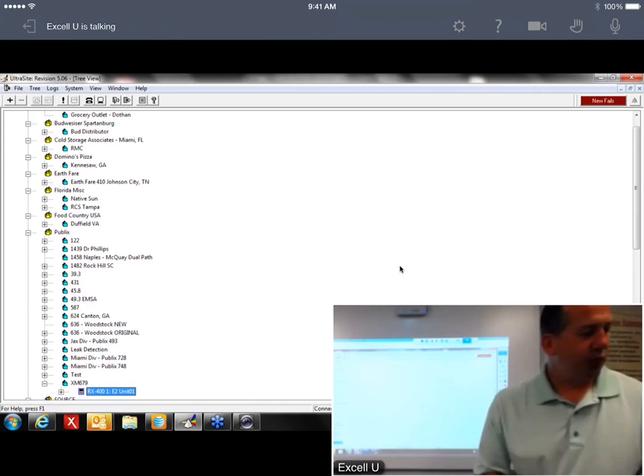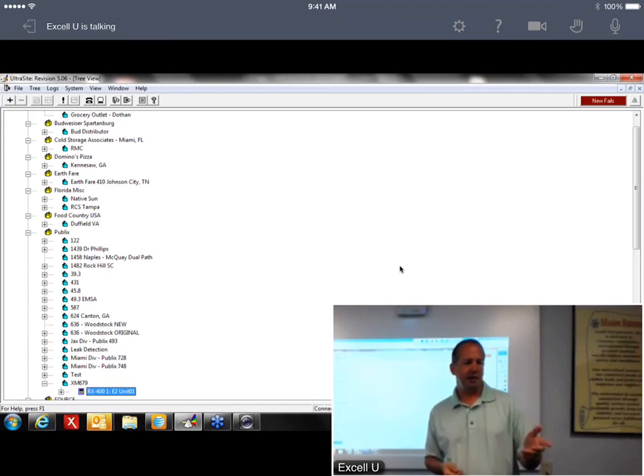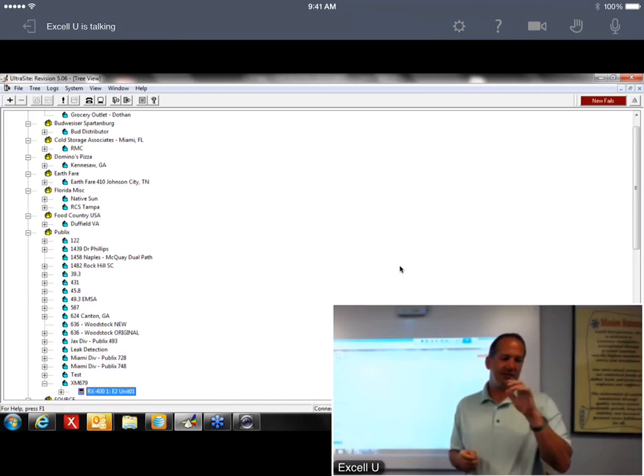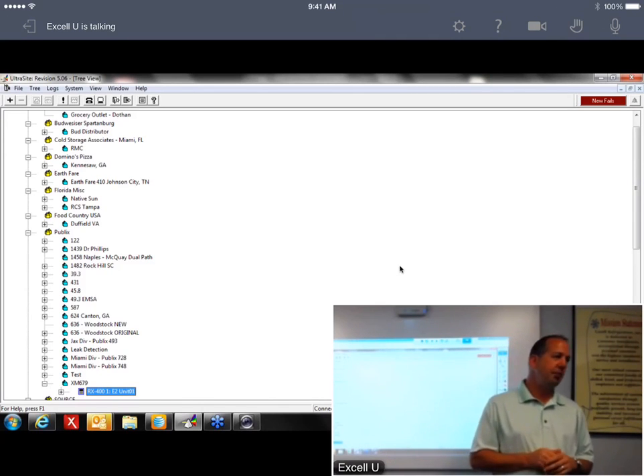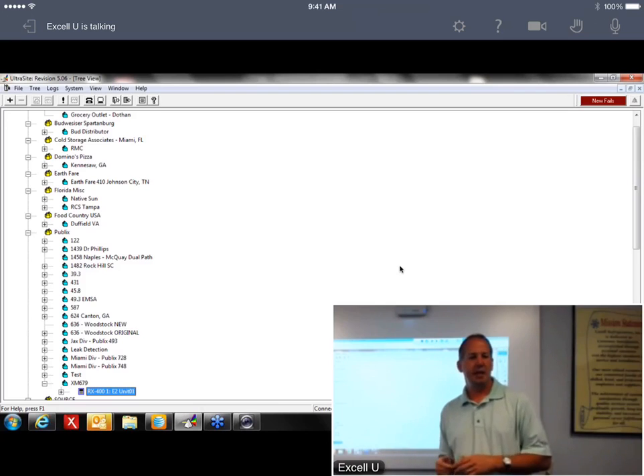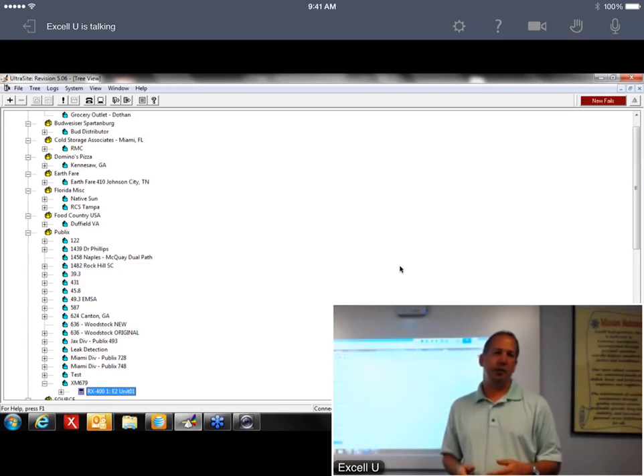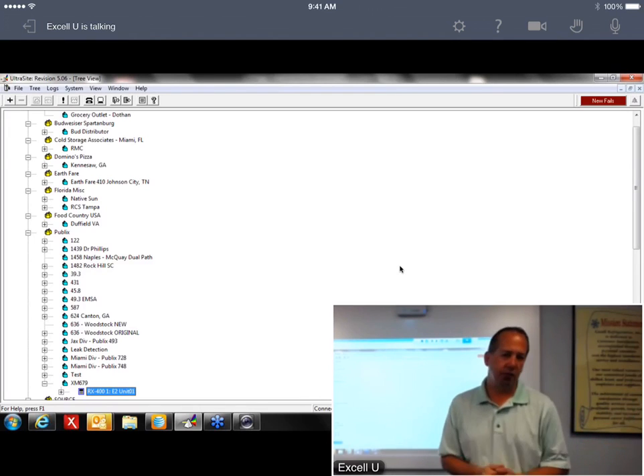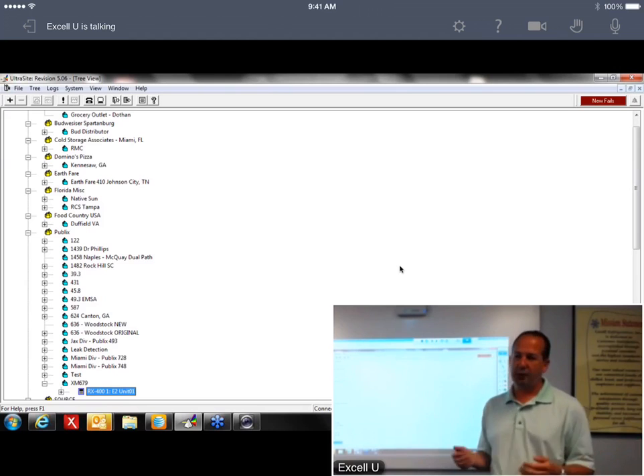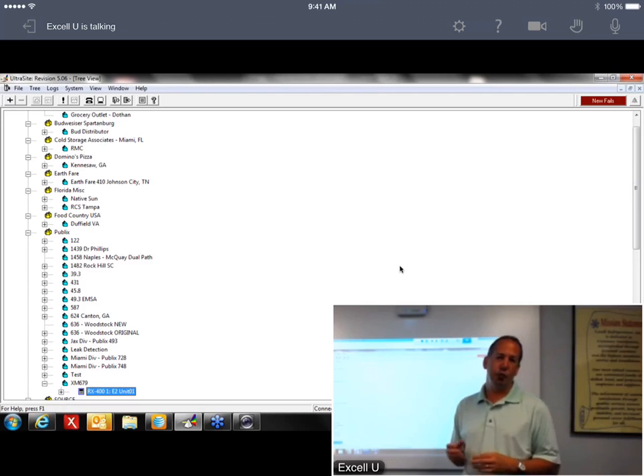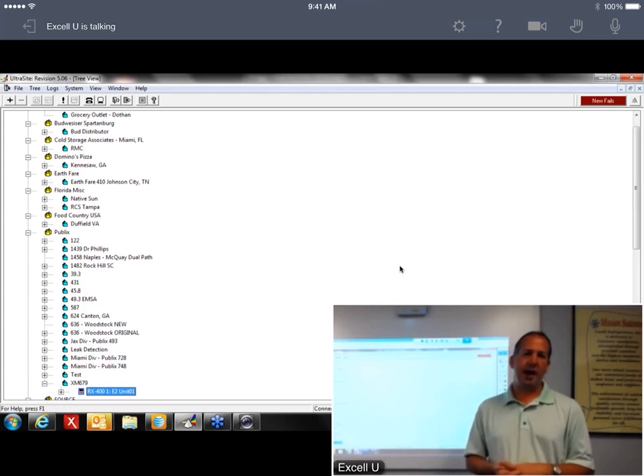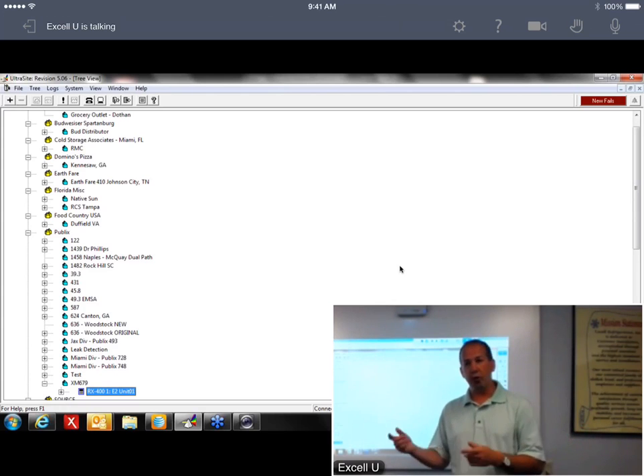That's one of the things I'm working with Publix on, retrofits. As of right now, Dixell isn't the best opportunity for a retrofit, because if you were taking an old CCB out, or a CC100 that failed, and say 10 years from now the CC100 fails and we don't have replacements for those, which I fully anticipate happening at some point, at this point it's not a real good retrofit opportunity because we have to put a transducer in, since right now it can't do coil-in, coil-out superheat.